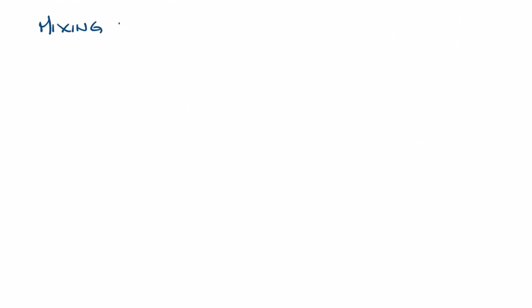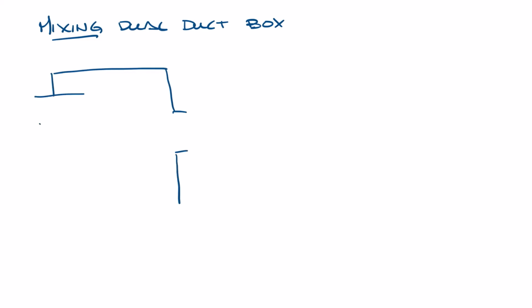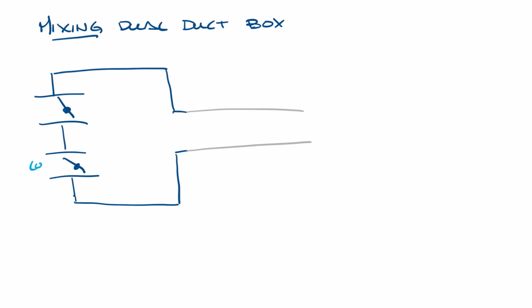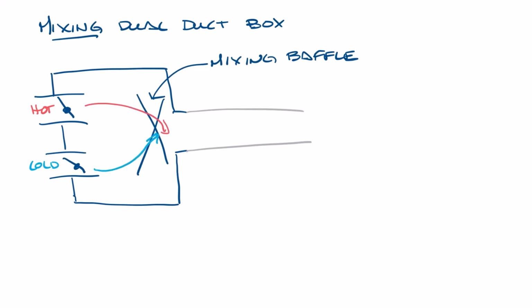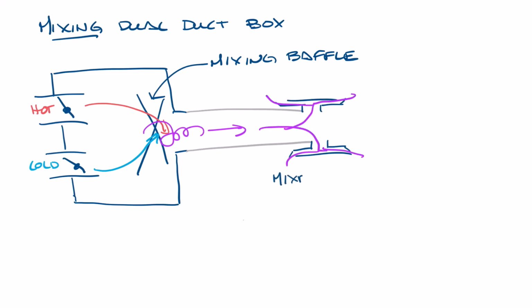The other type of dual duct box is a mixing dual duct box. As its name implies, the box mixes the hot and cold air streams. Just like all dual duct boxes, we have a discharge and two inlets, but inside the box there's an area for air streams to mix, typically with a mixing baffle to help the air get well mixed. The mixing baffle forces the two air streams together so that they can mix well before going out to the discharge and then into the space. So now we have two diffusers in the space. They are both getting the same blended temperature air.